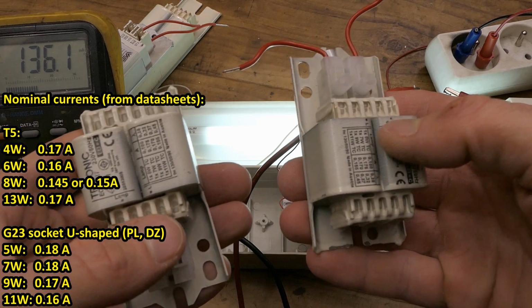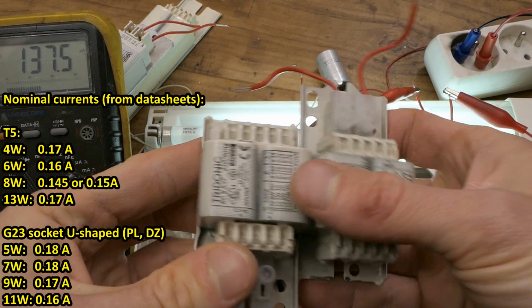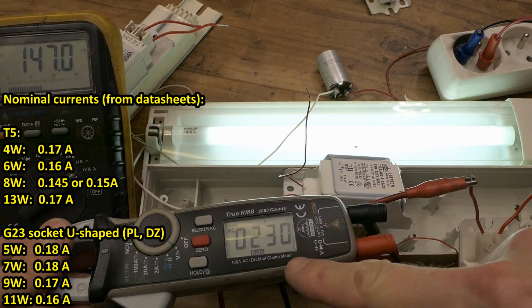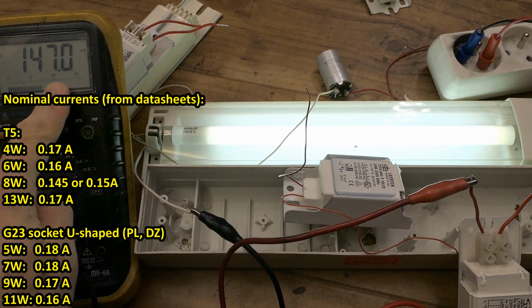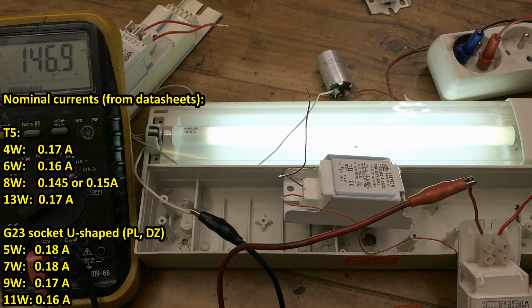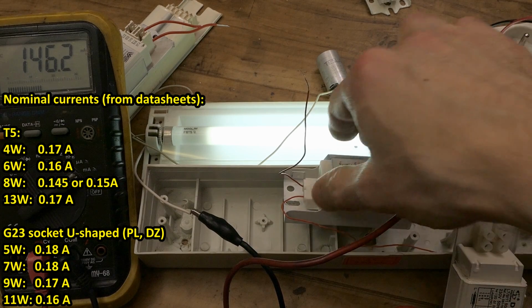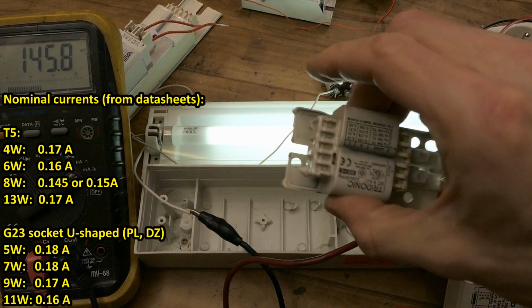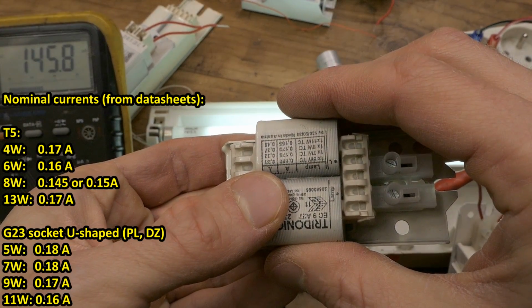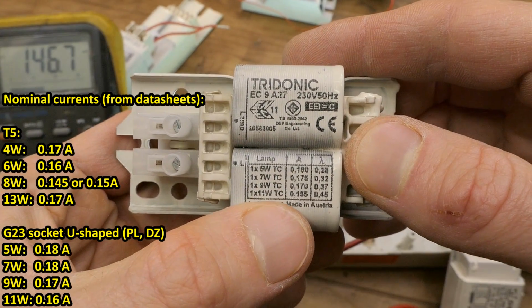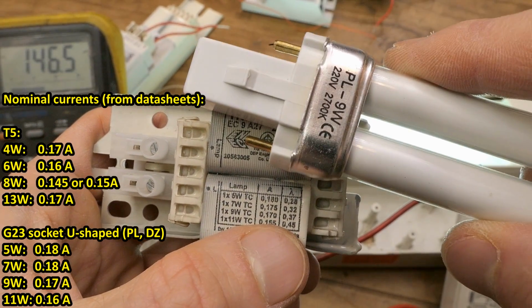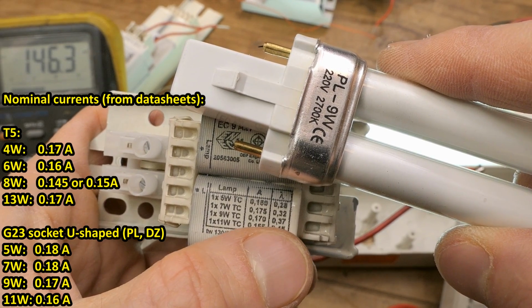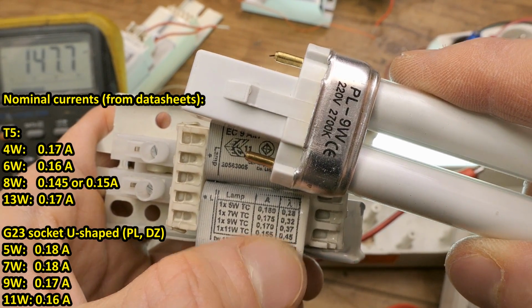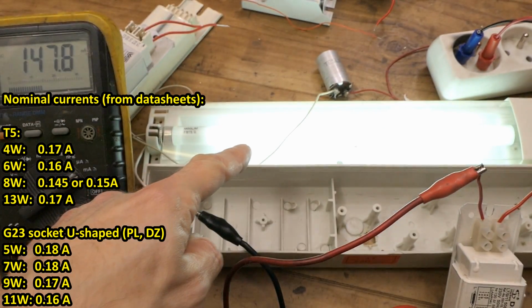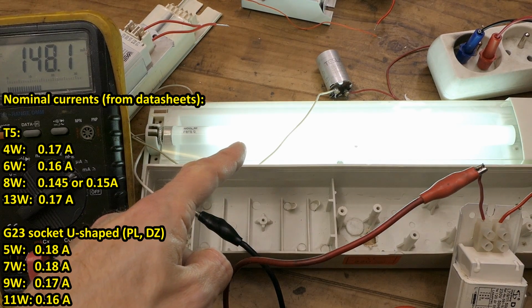So I can actually pick out the one that's closest to the current I need, and it's the nominal mains voltage. This one is actually spot on - it's running on this one now. This one is a bit higher, and this one is even more higher, which is obviously because it's meant to be a bit higher current. For the 9 watt tube, it's meant to supply 0.17 amps, and this one needs 0.15 or 0.145.